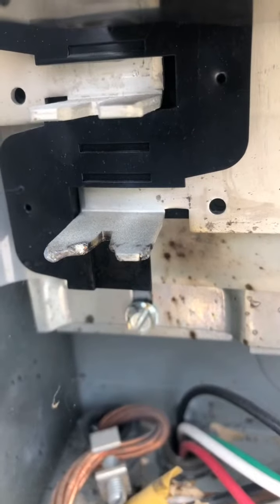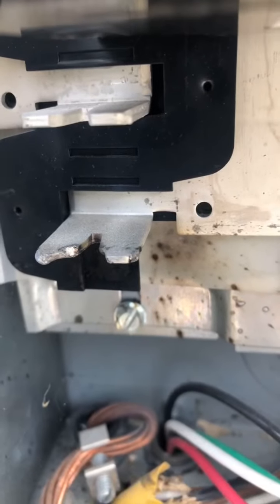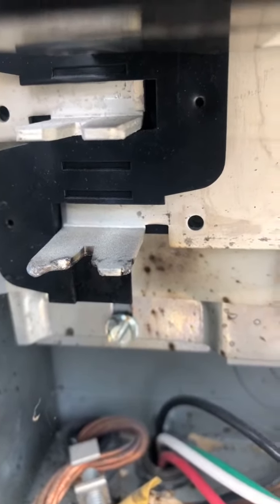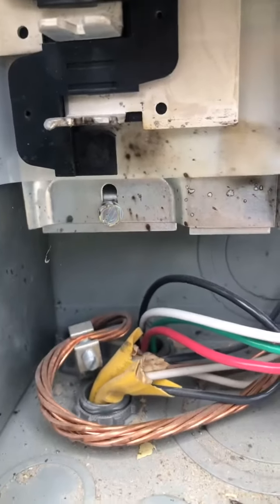Let's take a look at that. It's kind of hard to see, but you can see that left prong right there is a little bit melted — just from making a connection there. And you can see where the arc occurred on that back plate. We are going to recommend having an electrician look at that one right there above, and then look at this one.